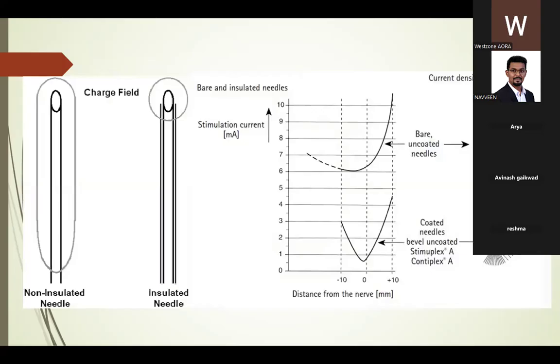As you can see, this is a non-insulated needle. The tip and the shaft are all conductive, so they cause current dispersion along the entire needle and local stimulation of the muscles. So the desired motor response is not accurate. In insulated needles, the complete shaft is coated with Teflon and only the tip is conductive. So you get a better motor response, which is precise.